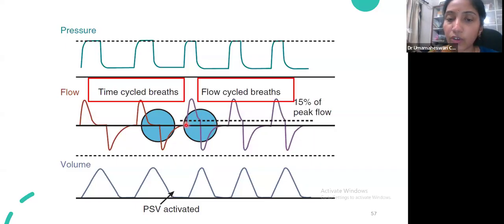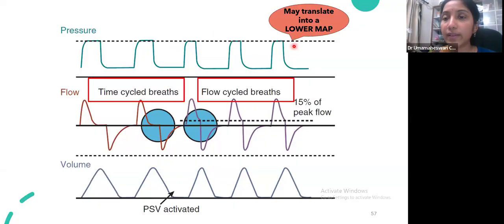So the inspiration is also controlled by the baby, because it is the trigger mechanism which identifies the baby's inspirations and starts the breath. The expiration is also controlled by the baby because it is flow cycled. Only the peak pressure is what you deliver. But beware, whenever you are putting on PSV, it is otherwise known as spontaneous mode. So you have to make sure that the baby's breathing effort is adequate. For example, if you want to continue ventilation for one more day for some reason, you can put on PSV. It is more baby friendly because both inspiration and expiration are controlled by the baby itself. Only the peak pressure is what we decide, and there is no fighting and no asynchrony. However, the disadvantage is that it can translate into a lower MAP.